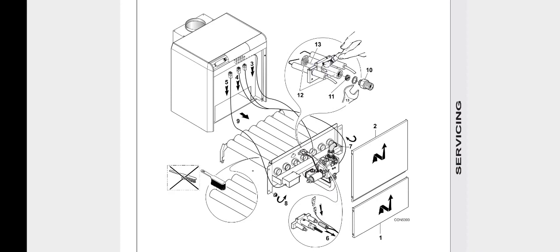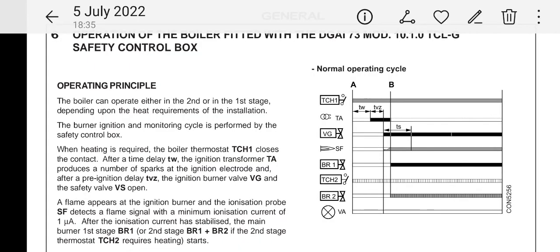On this particular unit, I just cleaned the pilot assembly and then also the burners. It was just a repair I was doing, it wasn't a full service. In a full service, it is good to take off the top and also give the unit a brush down through the boiler body. Here's some further details on the stage, or the operation principle of how the boiler goes through its sequence of operation. Also here is some further details as to what the display is about. The first and second stage is quite responsive, and you can get it into the two different stages. It responds quite quickly.